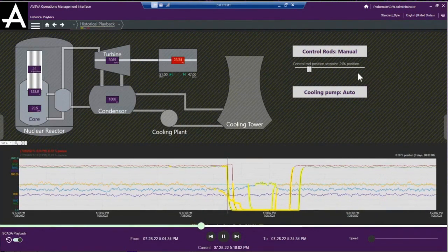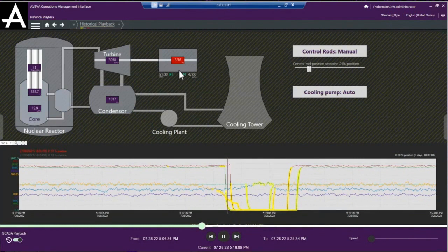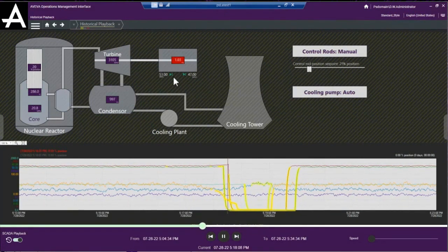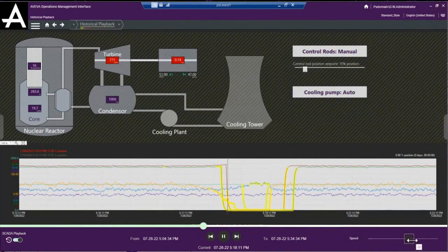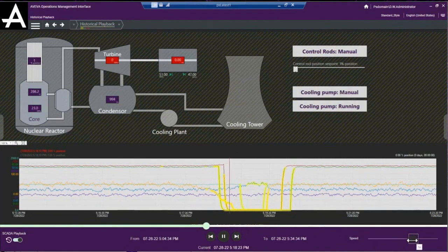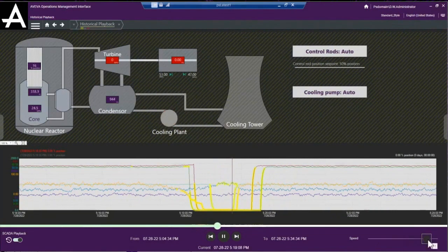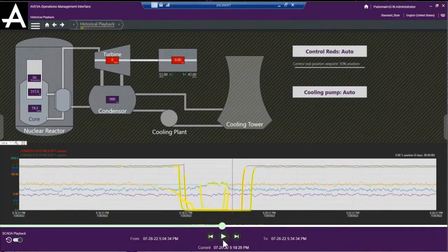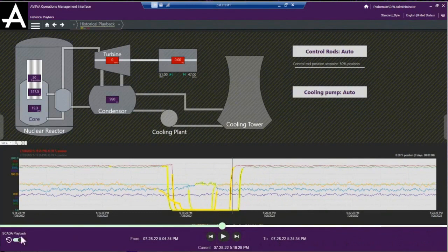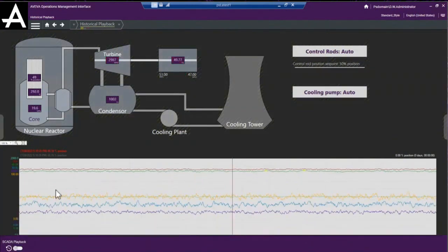Now, in the past, you would have known that something that wasn't historized would have given you an error on the screen. We did that on purpose. What we've done now is we allowed you to put something that's not historized, like those alarm limits you see there. They're not historized. You see a little play button there, a triangle, the line. That means that this is live data. That's just to make people aware that they're looking not at history, but they're looking at live data, even though they're in historical playback. For things like tag names and stuff, you can elect not to show that.